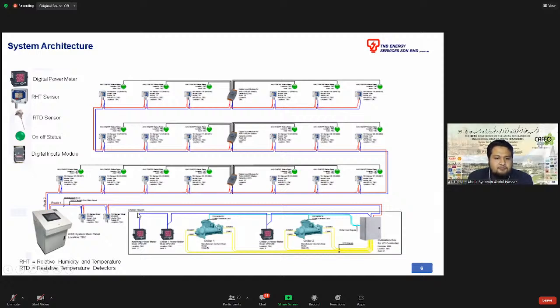Next, the RHT sensor. The rule of thumb is we install 1 RHT sensor per AHU, so we know the localized temperature. We also install an on/off status for each AHU, so we know which AHU is running and which is off.